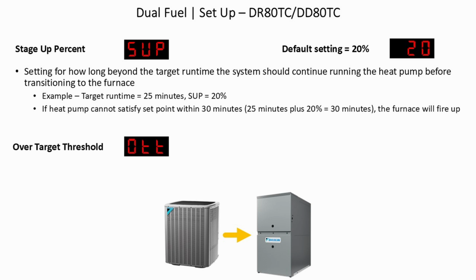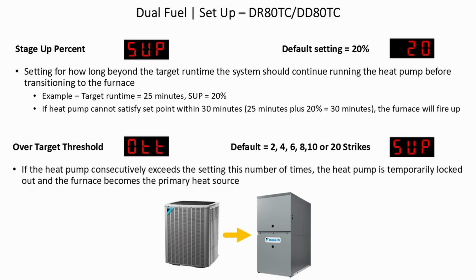Over target threshold, shown as OTT, default 2, 4, 6, 8, 10, or 20 strikes. If the heat pump consecutively exceeds the setting this number of times, the heat pump is temporarily locked out and the furnace becomes the primary heat source.